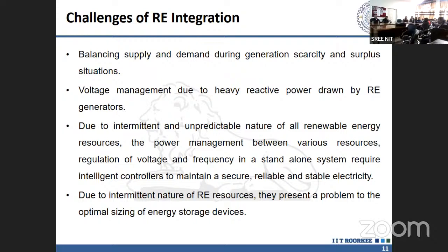Suppose you are in a standalone system. The solar is generating 10 kilowatt power, but your load is only 2 kilowatt. What to do with the extra 8 kilowatt? If you don't have storage, or even if the storage is full, sometimes you have to create a dump load—you have to waste this power. Otherwise, what will happen?